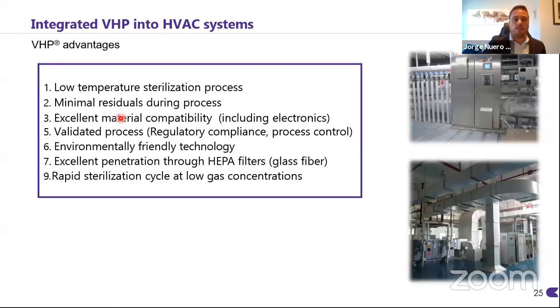What is the benefit of this? We have a very low temperature sterilization process. There is minimal residual, excellent material compatibility, including laptops, electronics, and so on. It is a validated process. Our team, after finishing installation, goes and makes sure that everything is running properly. It is an environmentally friendly technology. There is excellent penetration through HEPA filters, and it is a very quick technology. So it is a rapid sterilization cycle.